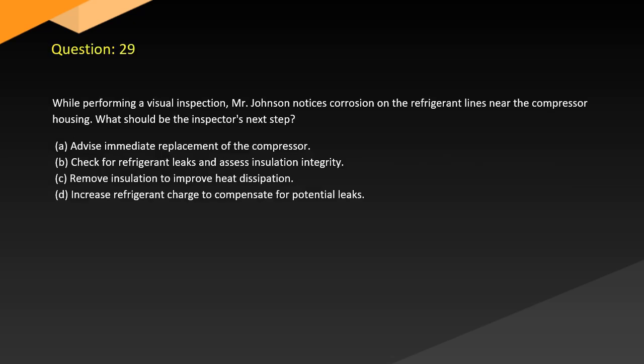Question 29. While performing a visual inspection, Mr. Johnson notices corrosion on the refrigerant lines near the compressor housing. What should be the inspector's next step? A. Advise immediate replacement of the compressor. B. Check for refrigerant leaks and assess insulation integrity. C. Remove insulation to improve heat dissipation. D. Increase refrigerant charge to compensate for potential leaks.